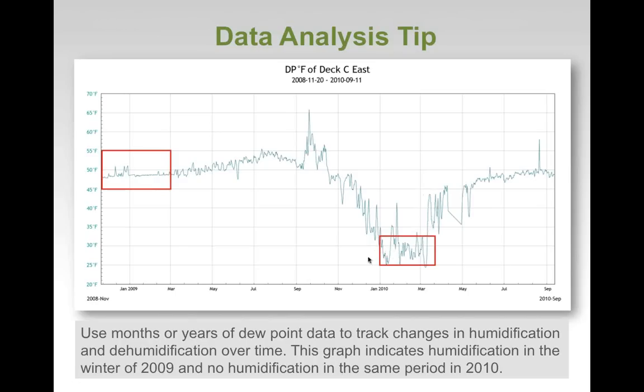They were able to bring it back on and operate it manually, which is what the bumps you see here turned out to be: the manual on-off to keep the humidity under control, or to have some form of humidity control in the space. And then you go back into the spring and summer here, and if we had a wider graph to show the following year, it actually was back around normal, which would be the 2009 level.